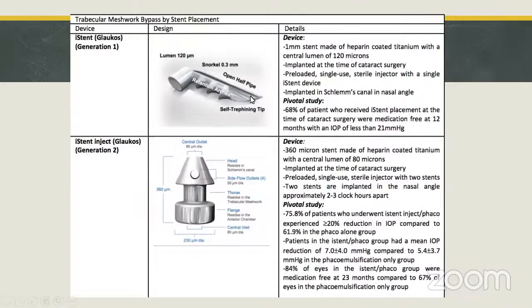The first generation eye stent is a 1mm stent made of heparin-coated titanium with a central lumen of about 120 microns. It can be implanted during cataract surgery and is a preloaded single-use sterile injector with a single device implanted in Schlemm's canal in the nasal angle. The second generation eye stent inject is a 360-micron stent, also heparin-coated titanium, with a central lumen of about 80 microns. It is preloaded, single-use, with two stents in the injector, implanted approximately 2 to 3 clock hours apart in the nasal angle.